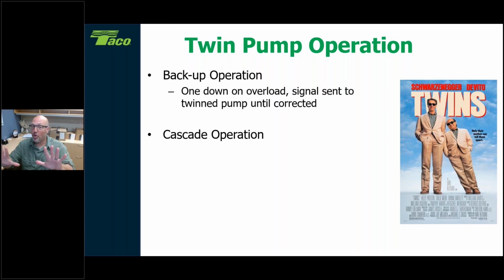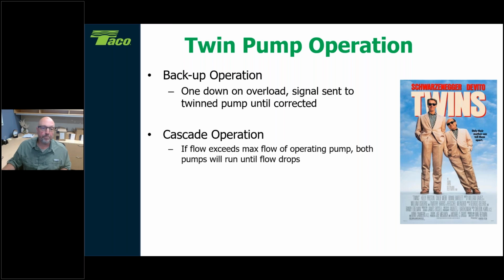So you got 2 smaller pumps here, and 1 pump starts to ramp up, all right, and once it starts getting close to that top, the second one kicks in. And then the first one's actually going to slow down, and then they both start to ramp up. All right, so it's all about trying to get that energy efficiency going on at the same time, because you've got a system that has a variable flow happening. It's not always the same flow continuously. So as it gets colder outside, that's when we need to ramp up with both pumps. So that's your cascade operation that we have built in.